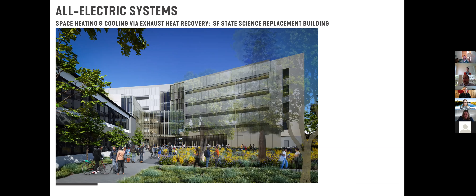On this particular project, what we're actually looking at is taking advantage of something else that occurs in a lot of labs. And this is not unique to labs, that actually happens at district energy plants as well, where you have a lot of heating and cooling that are actually happening at the same time. So if we think about all that outside air that we're bringing into a building to offset the hoods, there's still a lot of load inside the building that's requiring cooling.